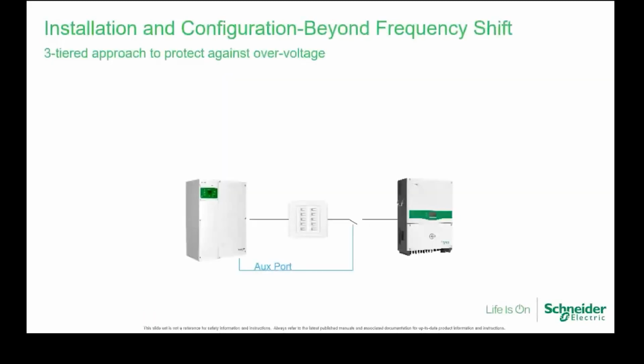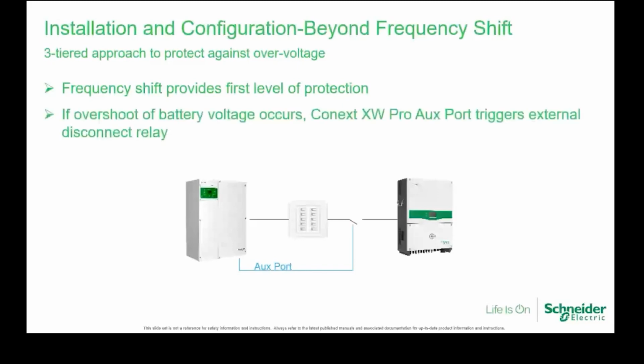So, a three-tier approach to protect against overvoltage. The frequency shift provides the first level of protection. Then, if an overshoot of the battery voltage occurs, the Conext XW Pro auxiliary port triggers an external disconnect relay so that you can then disconnect the PV inverter from the XW Pro. And the third level is your high battery cutout setting, where the maximum is 70 volts.